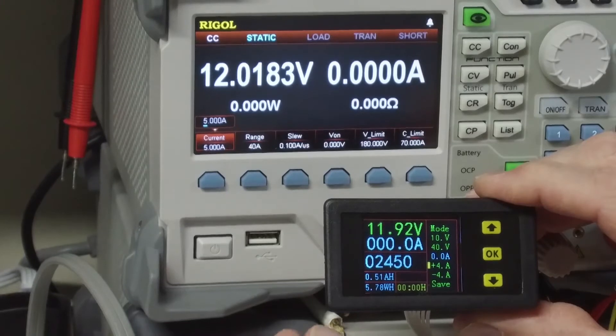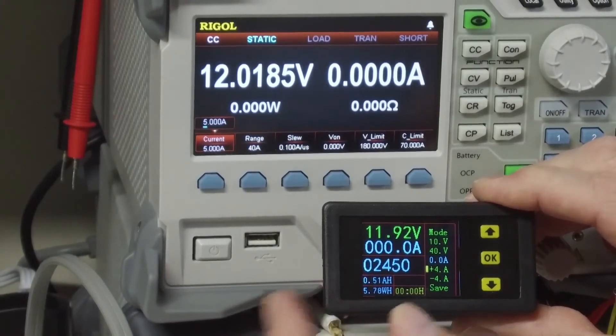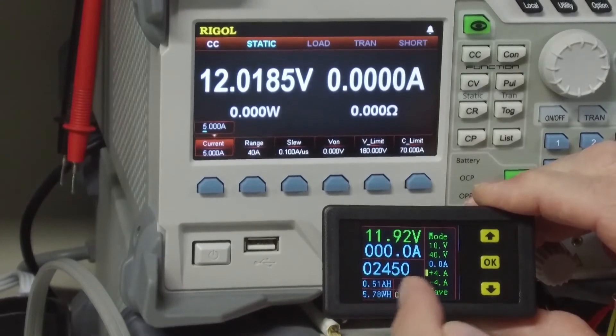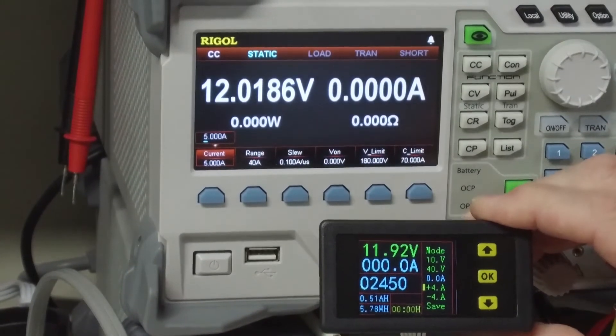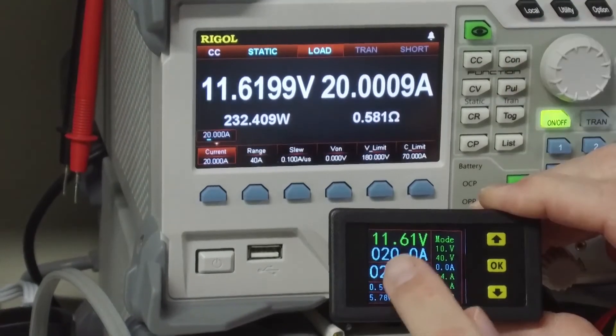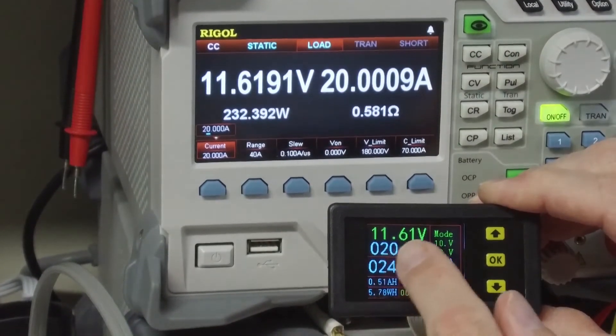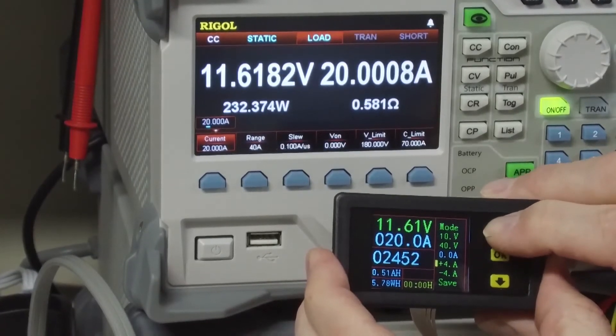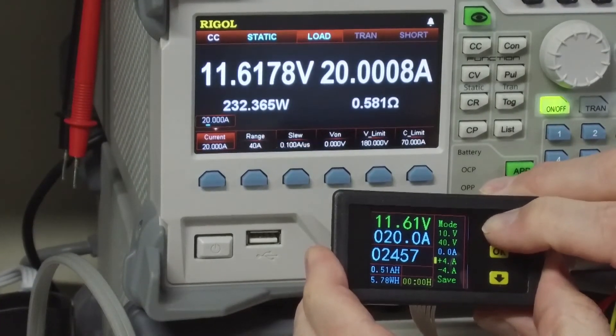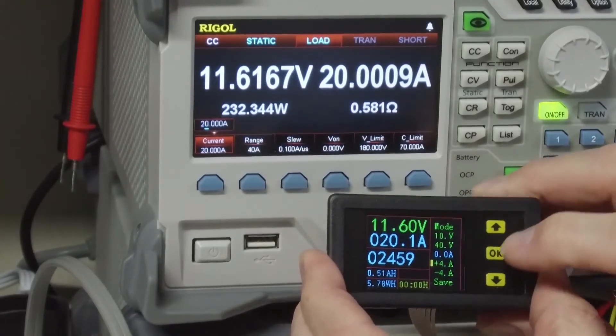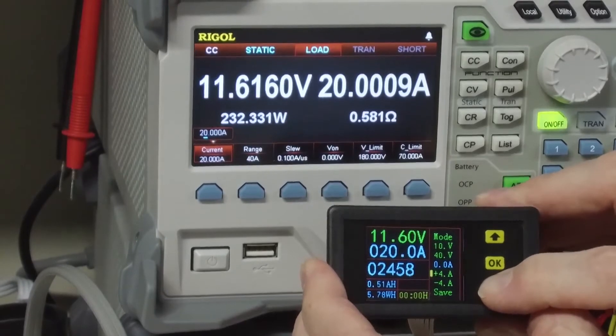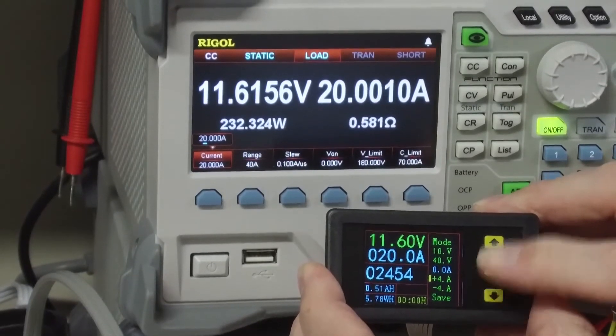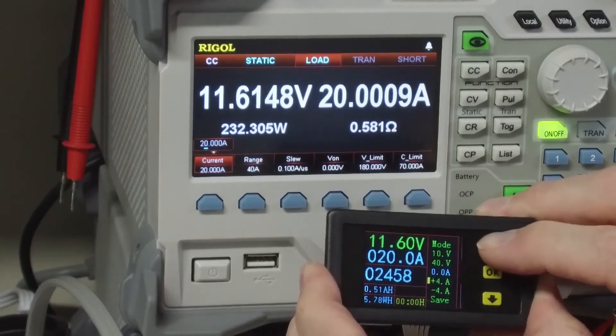If you calibrate at a higher current, you get more resolution. So what I am going to do is I'm going to run my supply up to, say, 20 amps. We can see that from my previous calibration that it is on pretty close. But I can push these numbers and release. And see now it's saying 20.1 amps. I can go the other direction. And you might need to play with it a little bit.